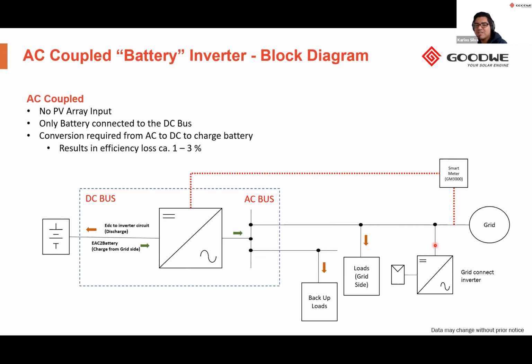Strictly speaking, our AC coupled battery inverter is not a hybrid because it does not have its own direct PV array connection. Therefore, it's generally referred to as a battery inverter. But what is interesting to know is that this battery inverter is bidirectional. Therefore, any excess power that is generated by the grid connect inverter will be able to be fed into the battery bank as well. So if the loads are using half of the PV power that's generated, then half of the PV power will go back into the battery. And when the battery is full, the grid connect inverter will be able to export back into the grid.